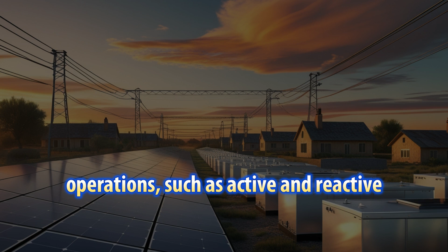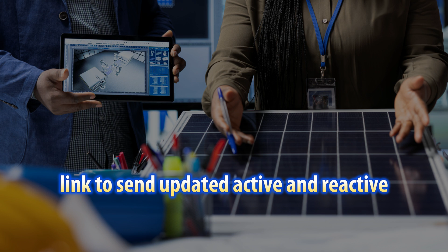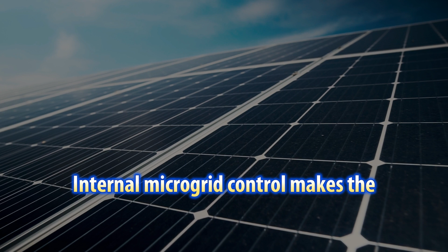known as internal microgrid control, is implemented centrally. The microgrid central controller is responsible for gathering information about the distributed generating unit's operations, such as active and reactive power data. The microgrid then uses the communication link to send updated active and reactive power setpoints to all local controllers, such as the controllers of the energy storage units and distributed generators, based on the microgrid specifications. Internal microgrid control makes the decisions regarding how the distributed generators should operate in the photovoltaic microgrids.